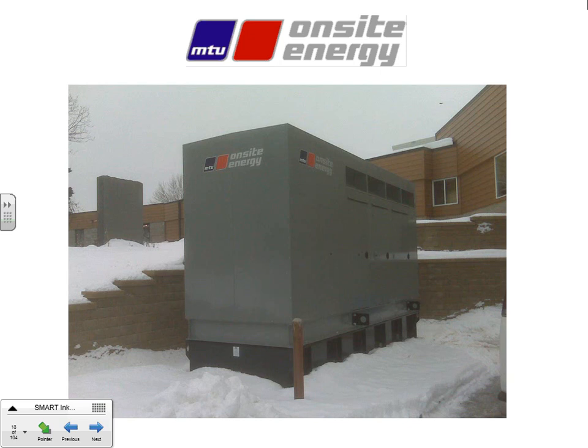Again, a different style enclosure. This is a smaller unit, and I'll use the pointer here; this is actually an upduct, this portion of this enclosure. So in a generator set design, you have a fan that operates a little differently than the one in your car. When you're moving down the road in your car, the radiator brings the air in and it moves across the engine, hits the firewall, and goes underneath. Well, when there's no motion, you have to create an airflow. And all they do is make it, instead of a sucker type fan in a car, they put a pusher type fan, and the air is pushed through the radiator to cool it.